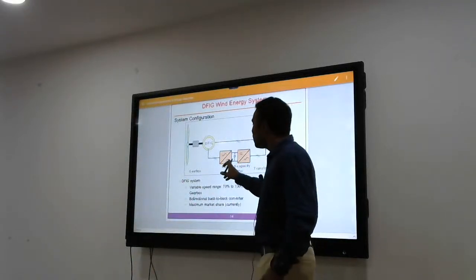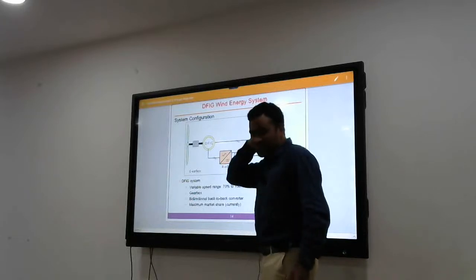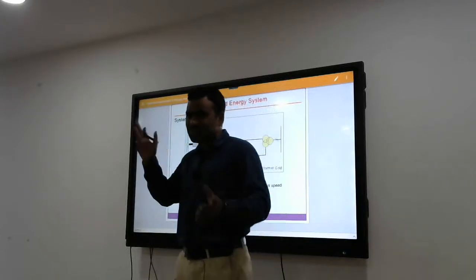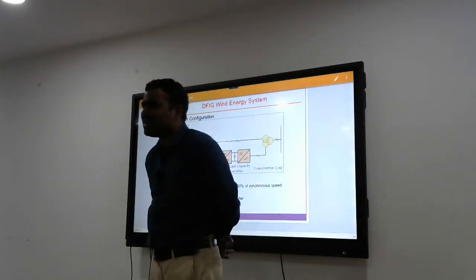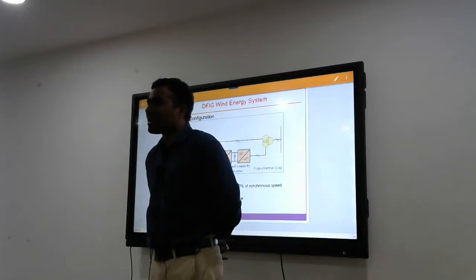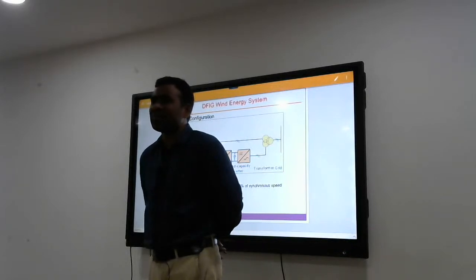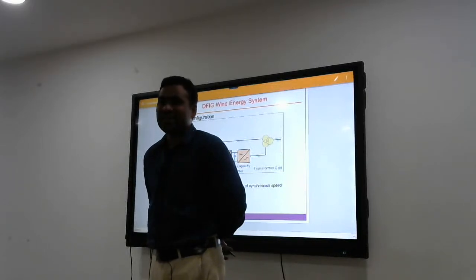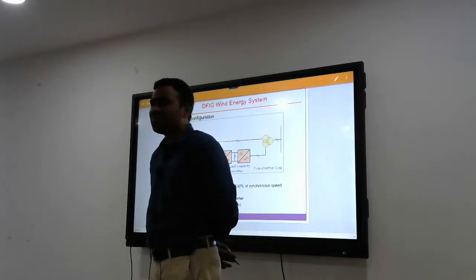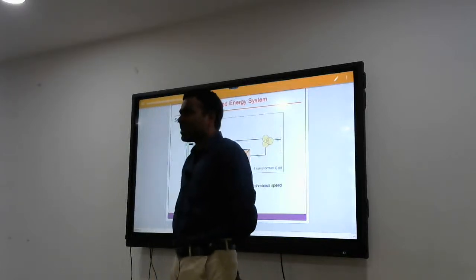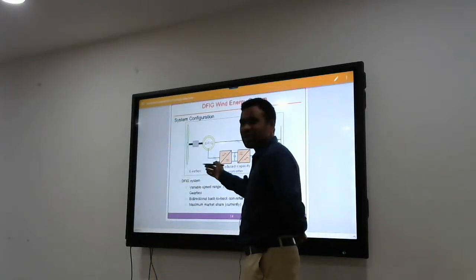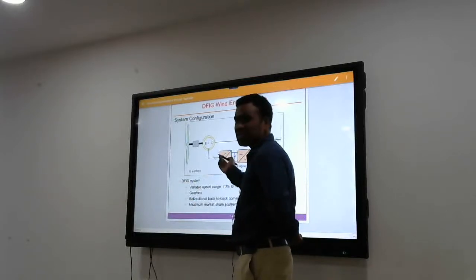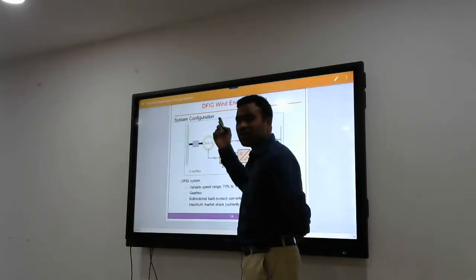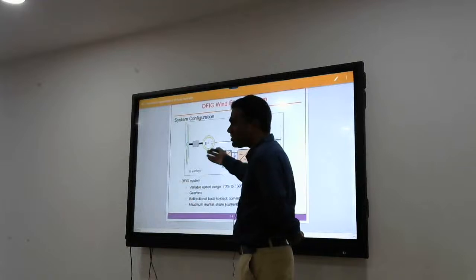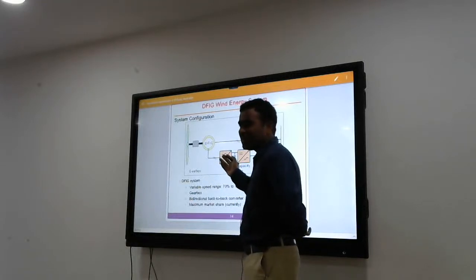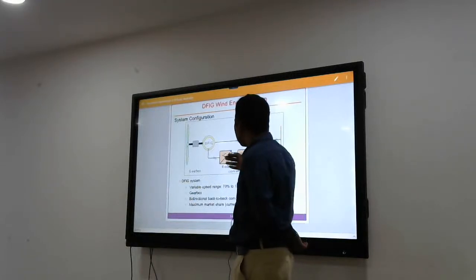This is very good, because suppose my machine is a 10 megawatt machine. In the previous case, the converter that is required is 20 MVA. But in this case, for 10 megawatt, you require 3 MVA plus 3 MVA, 6 MVA. There it is 20 MVA. So the cost will be very less in case of DFIG as compared to other topologies.